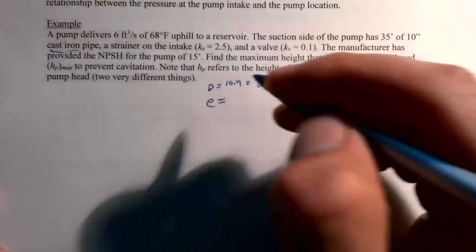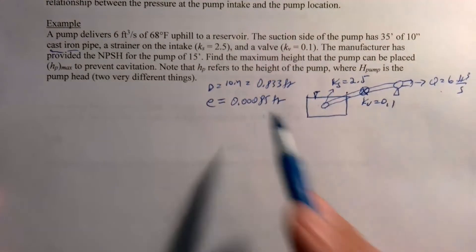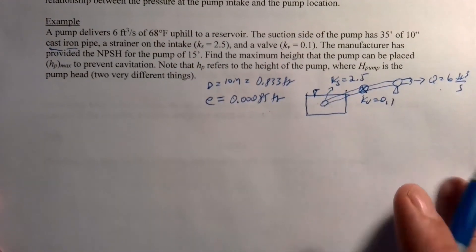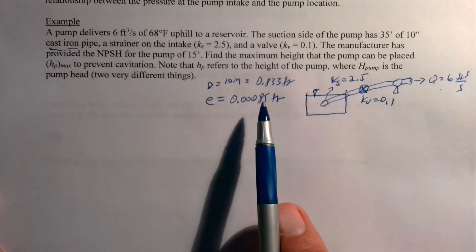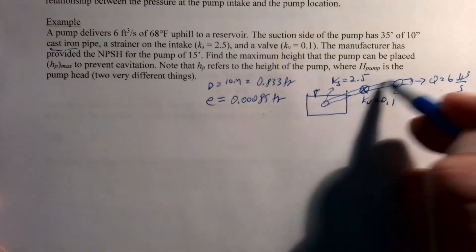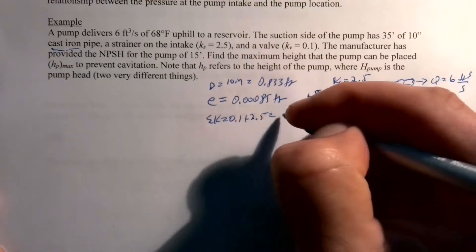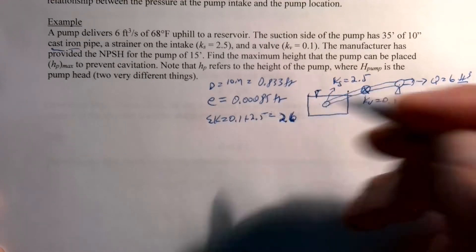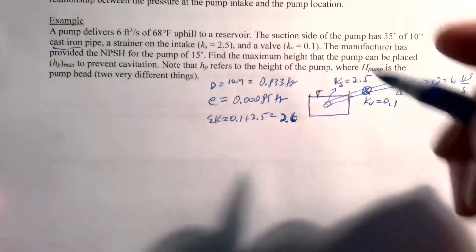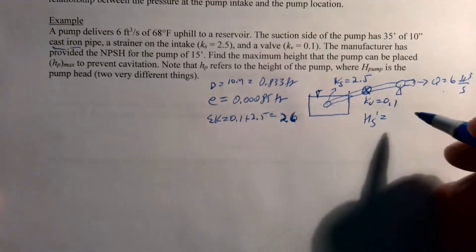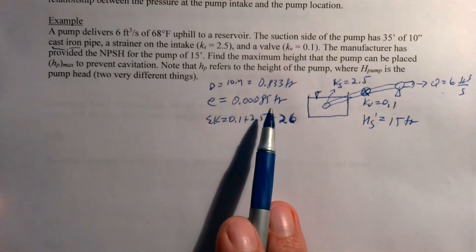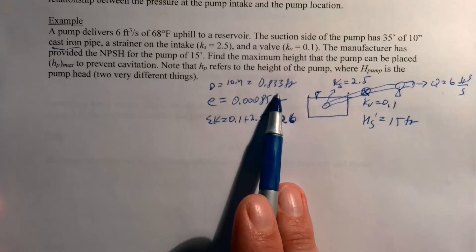The diameter is 10 inches, which equals 0.833 feet. It's cast iron, so our roughness height ε is 0.00085 feet. Working in US units. The sum of minor loss coefficients is K_v + K_s = 0.1 + 2.5 = 2.6. And the net positive suction head HS prime is given as 15 feet.